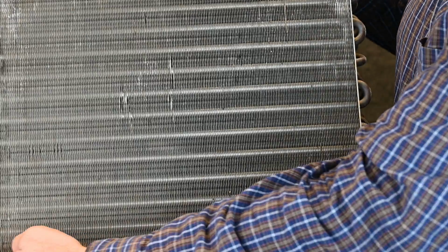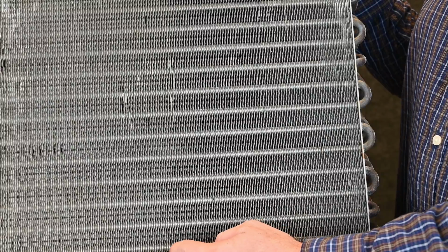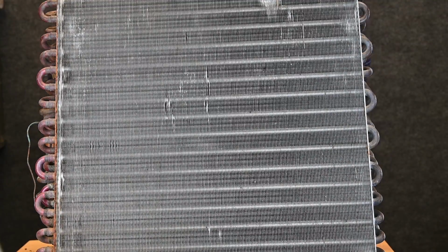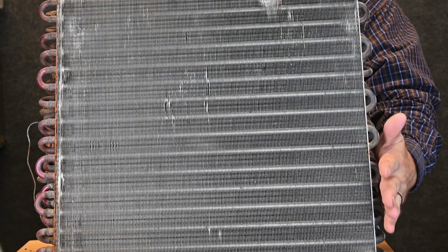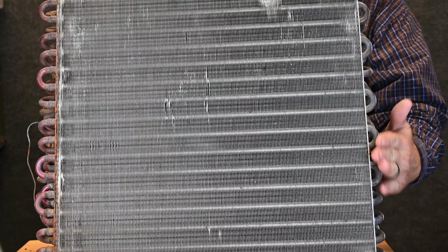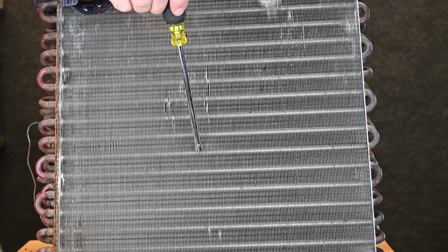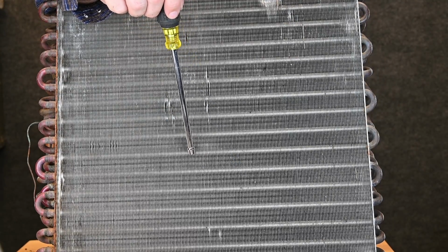Sometimes you'll see where this tubing runs through, it could even be leaking in the center of the tube. You're only going to be able to see this side right here, the front side. This you can kind of see with the mirror, but this is going to be the back side. It's going to be very hard to see. So if you have a refrigerant leak on this back side, it can be very difficult to find that leak. So we're going to talk about leak detection later on, but if you have a leak over here in the center tube, do you think you can fix it?